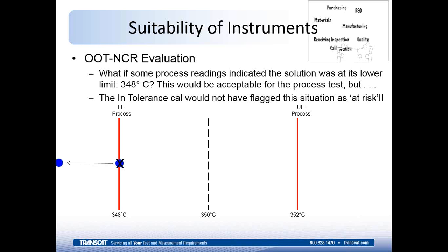What if some of the process readings in that 1-year interval were at 348 degrees? And now you found out that that instrument was reading high and it's adjusted back down. If you went back and were able to measure those process measurements, they would be less than 348 and they would be out of tolerance. But the in-tolerance calibration would not have flagged that situation as being at risk. So you could have some risk in your product, and process measurements for those particular measurements would be bad. So again, that whole scenario that I just went through was talking about using an instrument that has the same accuracy as the tolerance of the process. And that's another reason why you don't want to do that, because if you get any drift in the instrument, you're going to have drift in where your measurements were for the process. And that could throw a lot of them out of tolerance, and you wouldn't even know it.